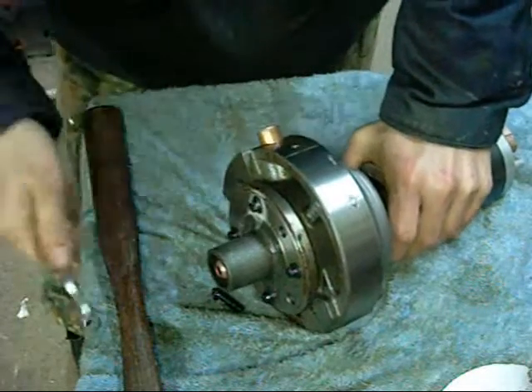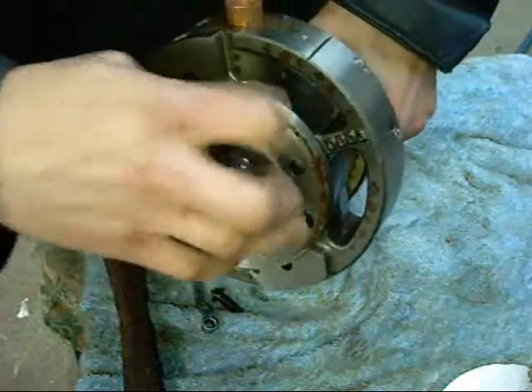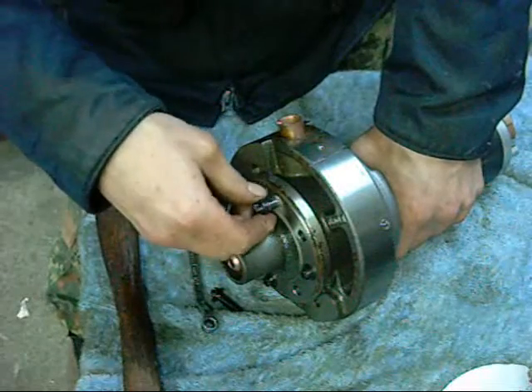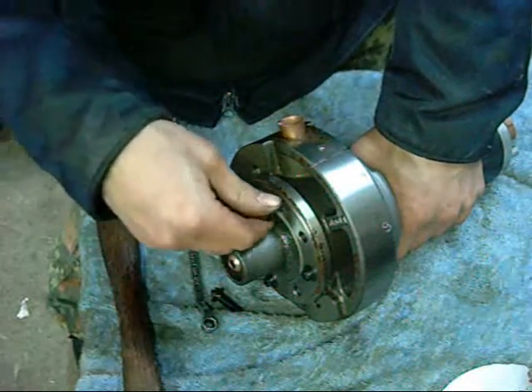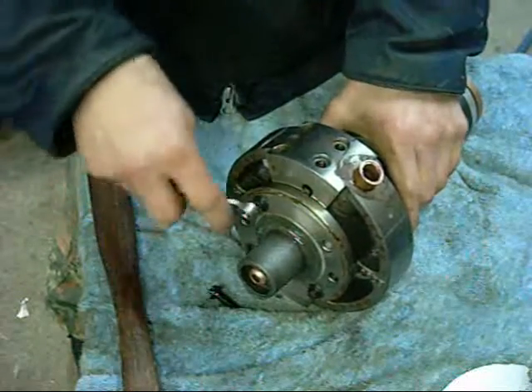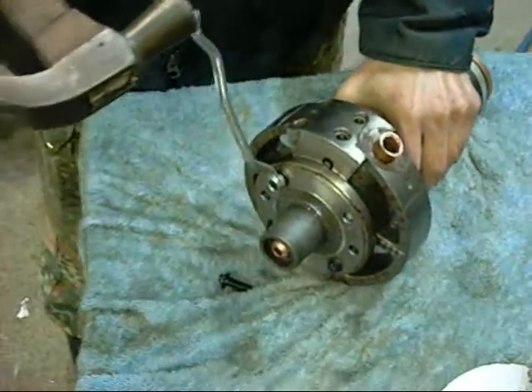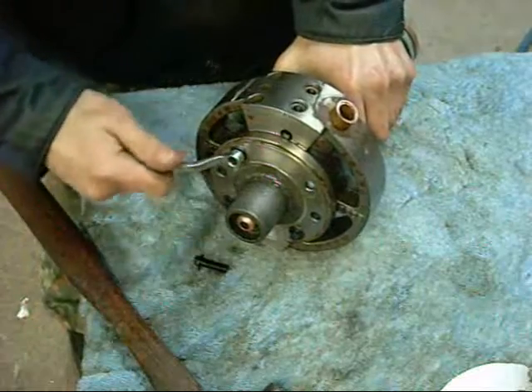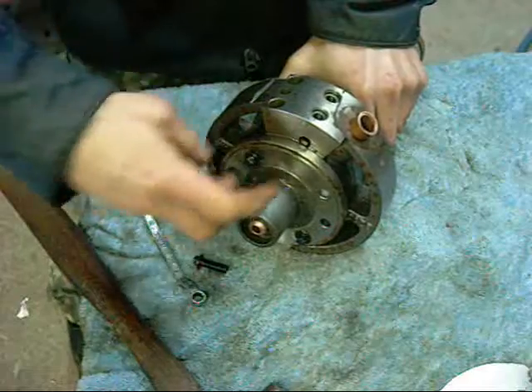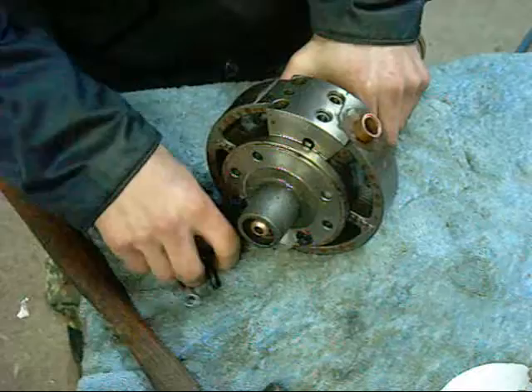That's why you wear goggles — a lot of refrigerant and oil foaming out from under these bolts, popping down under a bit of gas pressure. That's a good old R22 for those tree huggers out there. Ain't nothing you can do about it either. It's just pissing out as you screw it out.